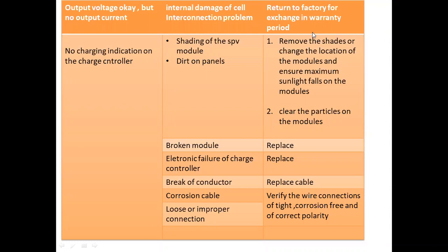These are the faults in the module: output voltage okay but no output current. The local internal connection damage means we will replace the module. These are the two situations.